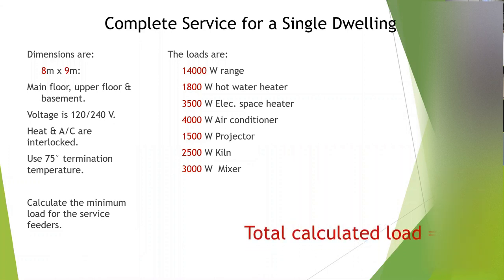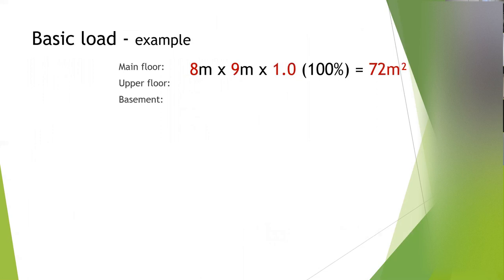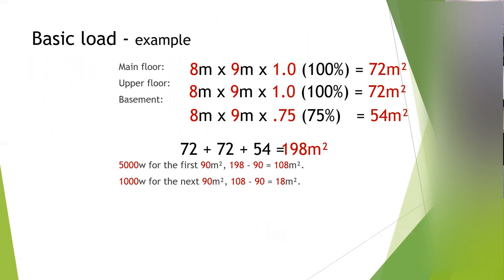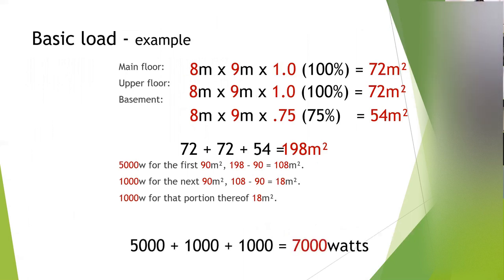Did you get a total load of 19,625? Let's go through it. For the basic load — same calculation as before. Main floor 8×9 × 100%, upper floor 8×9 × 100%, basement 8×9 × 75%. First 90 m² = 5,000 watts, next 90 m² = 1,000 watts, excess 18 m² portion = 1,000 watts. Basic load: 7,000 watts.